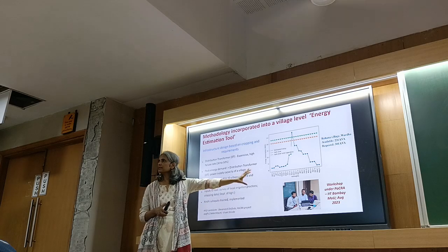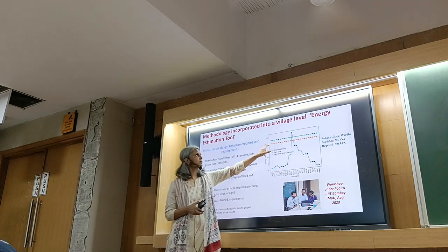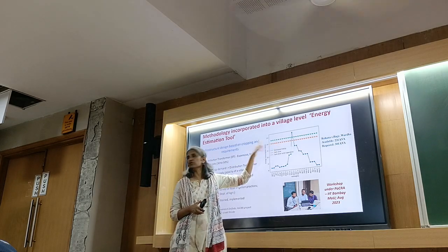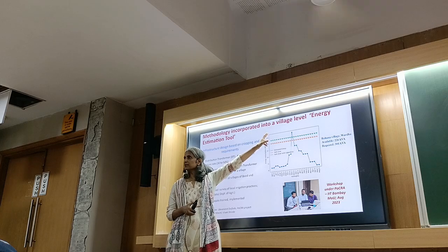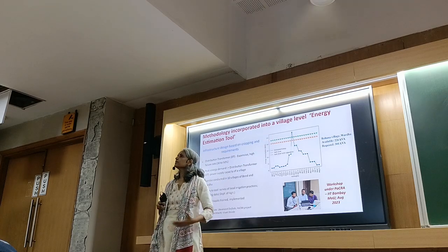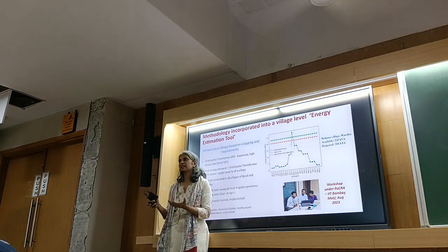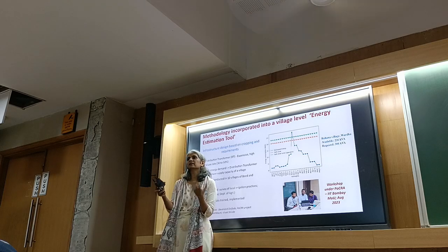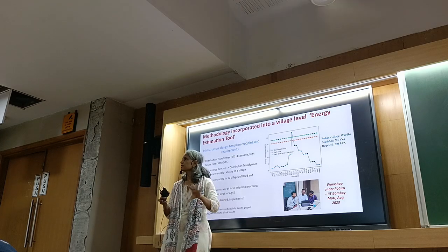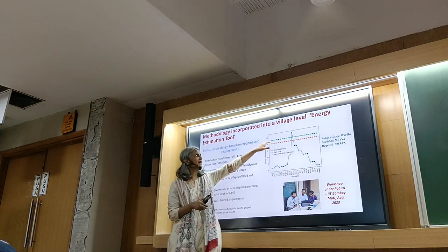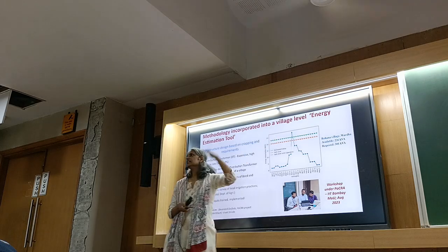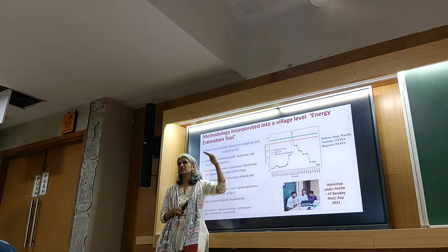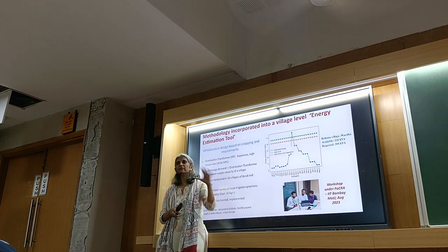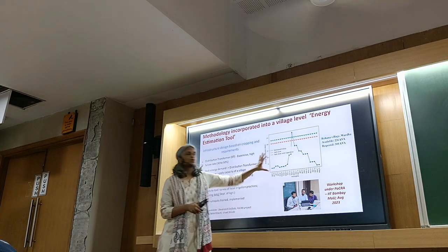Now the current capacity in this village allows a safe usage of energy of 20, but the requirement is much more. If all farmers install capacitors on their pumps, it essentially reduces the capacity requirement for a certain energy dispersal, so your safe zone would increase a little — a bit more energy could be supplied to the farmers.